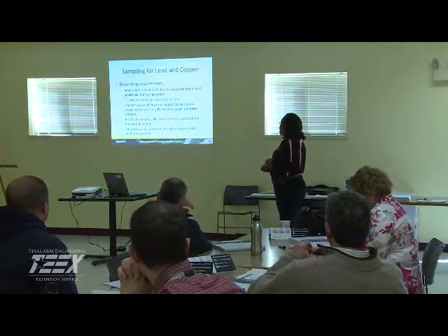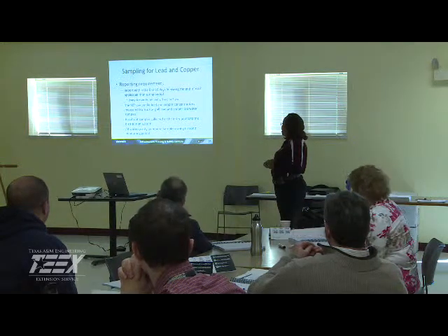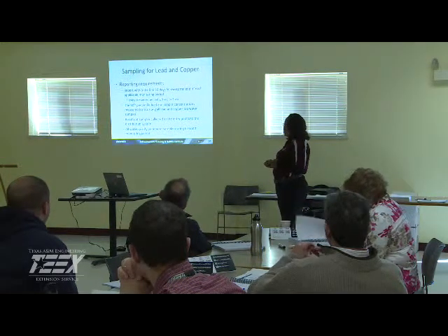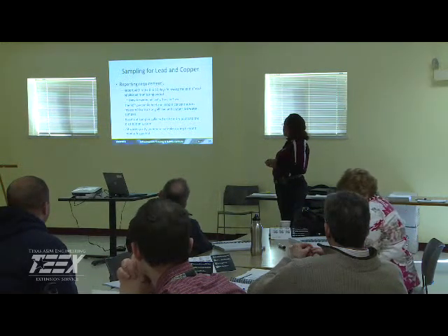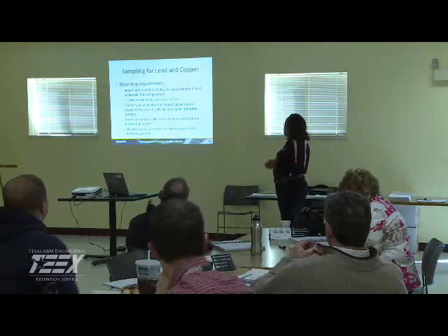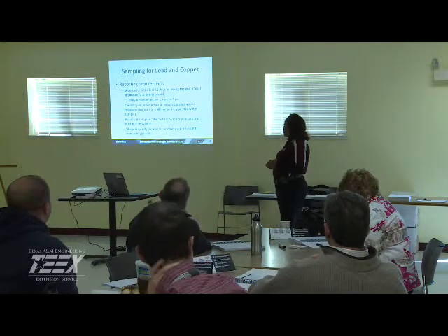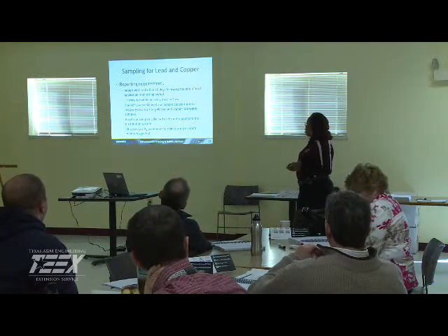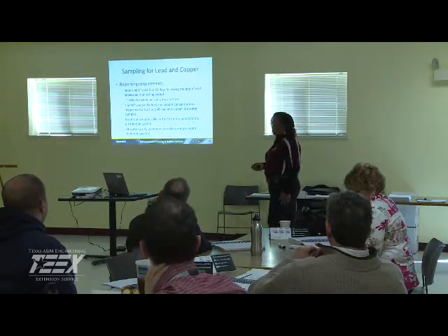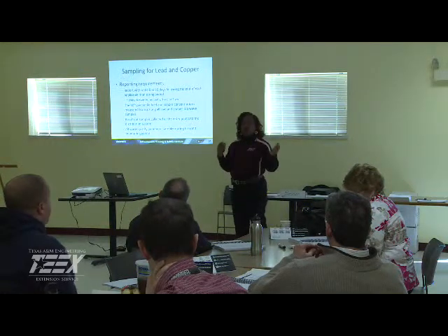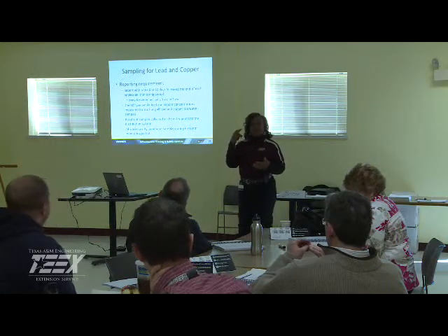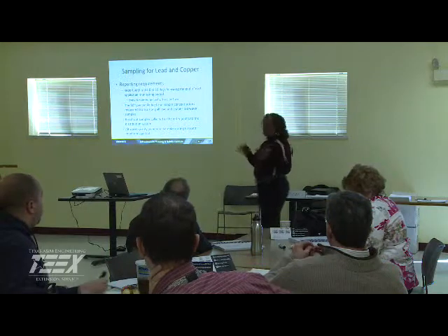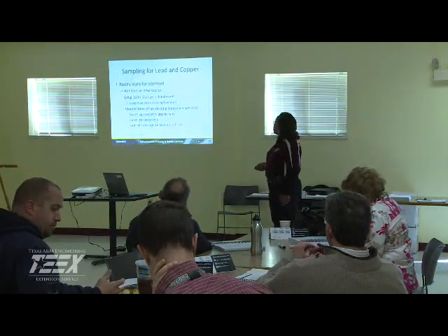The 90th percentile lead and copper concentration measured from among all lead and copper water tap samples is submitted. Results of the samples collected at your entry points to the distribution system, as well as all water quality parameters during the 6-month monitoring period. Again, water quality parameters: the pH, conductivity, temperature, those parameters. All of that's required.